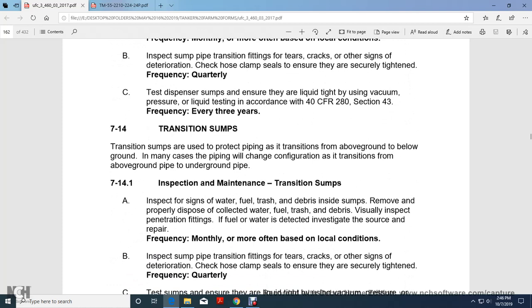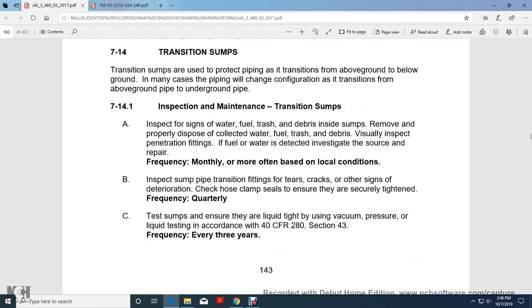Test dispenser sumps. Ensure that they are liquid tight with vacuum, pressure, or liquid testing according to Title 40 CFR 280, Section 43, with a frequency of every 3 years. Transition sumps. Transition sumps are used to protect the piping transition from above ground to below ground.